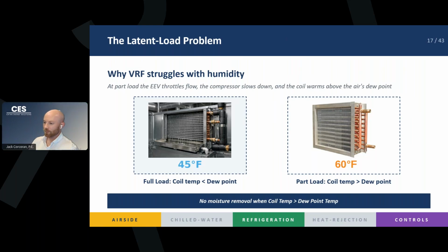So that is a drawback of our VRF systems that definitely needs to be put into consideration when you're designing these systems. It's great at full loads, but our coil temp is going to drift above the dew point when we're at part loads. Just another thing to think about with these systems.